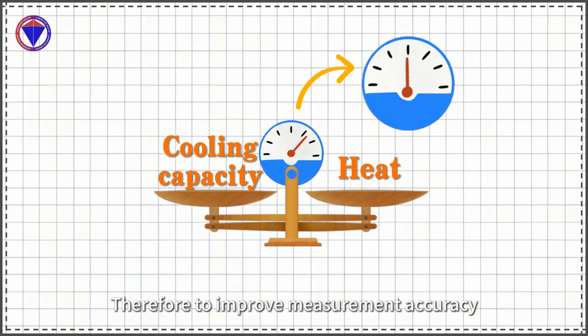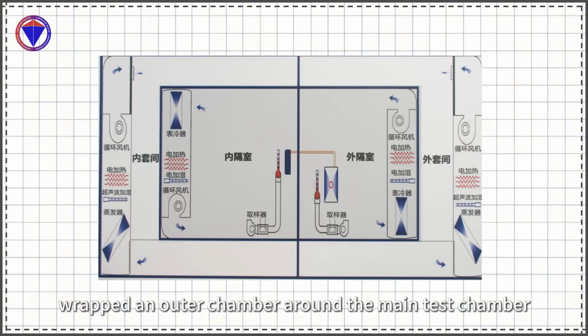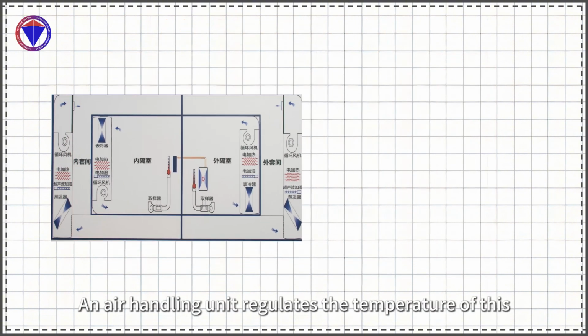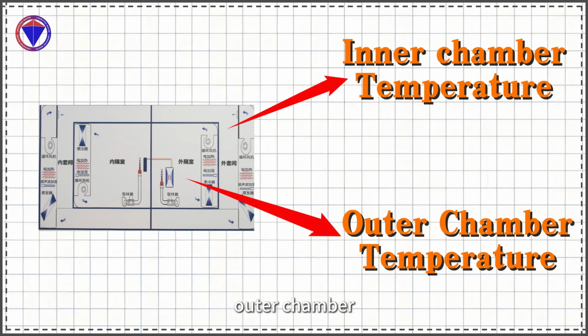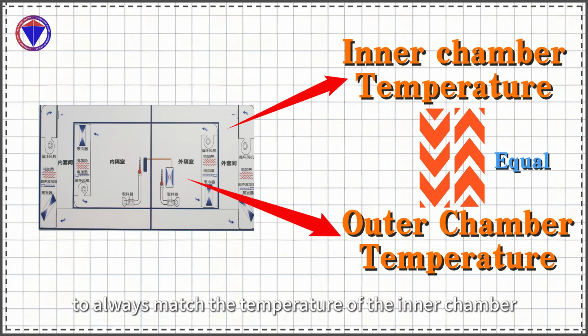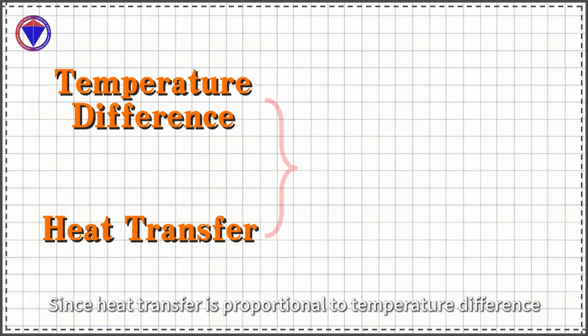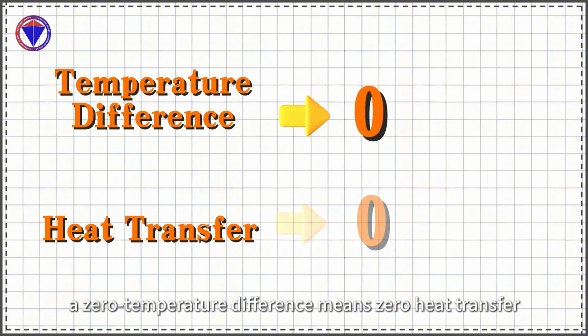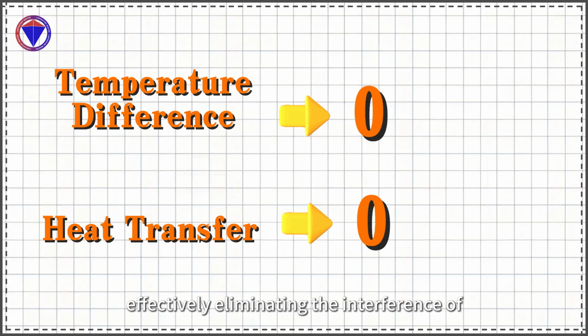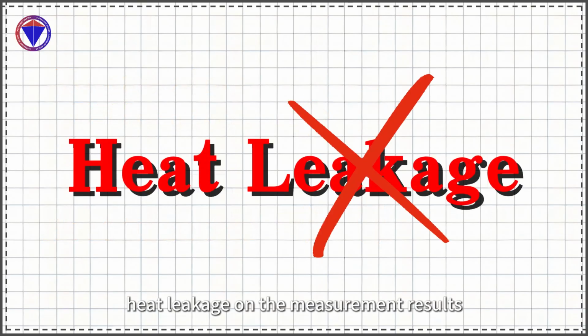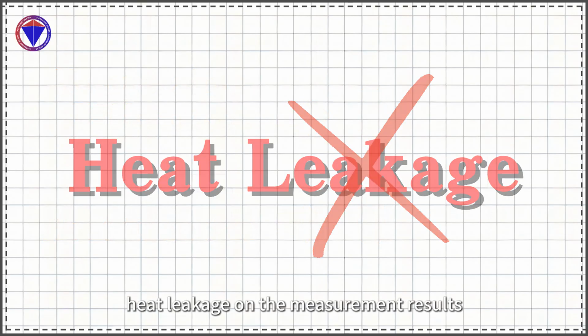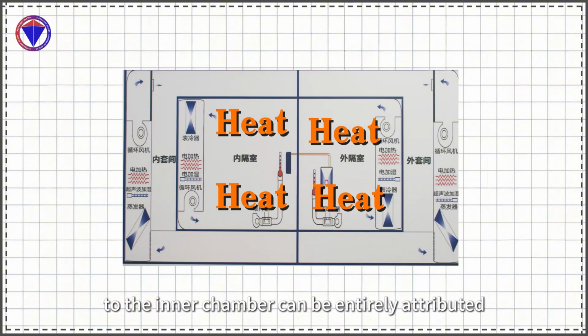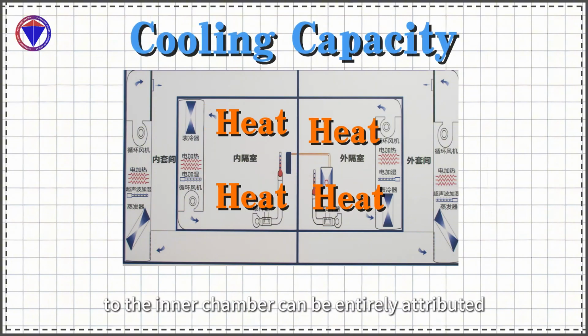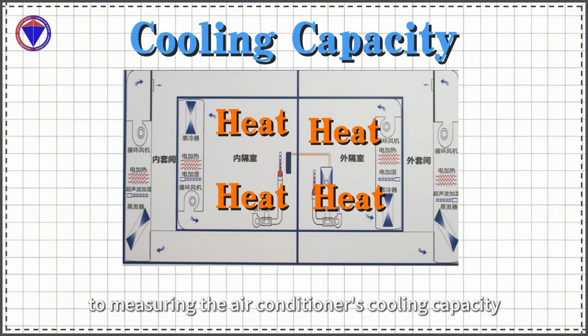Therefore, to improve measurement accuracy, an outer chamber is wrapped around the main test chamber. An air handling unit regulates the temperature of this outer chamber to always match the temperature of the inner chamber. Since heat transfer is proportional to temperature difference, a zero temperature difference means zero heat transfer, effectively eliminating the interference of heat leakage on the measurement results. Thus, the heat added to the inner chamber can be entirely attributed to measuring the air conditioner's cooling capacity.